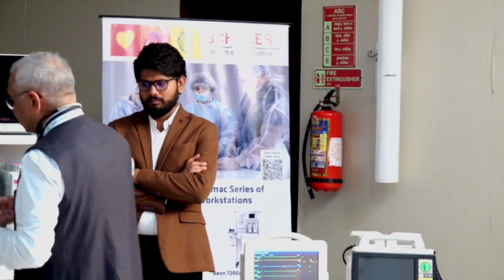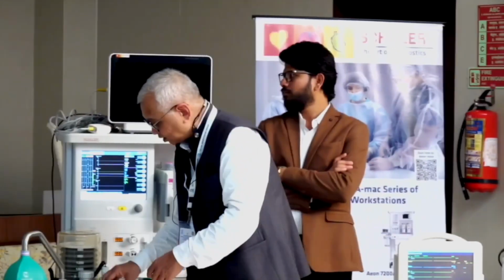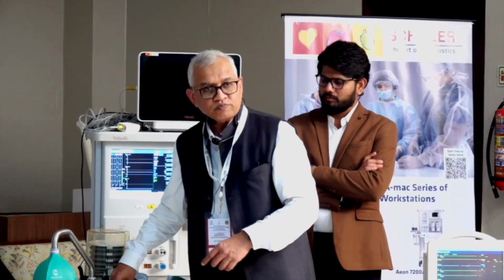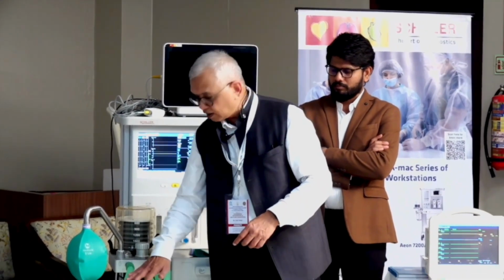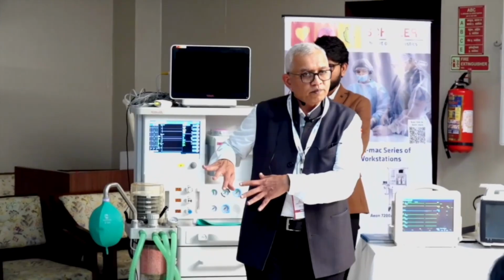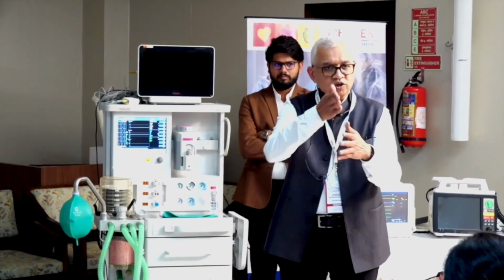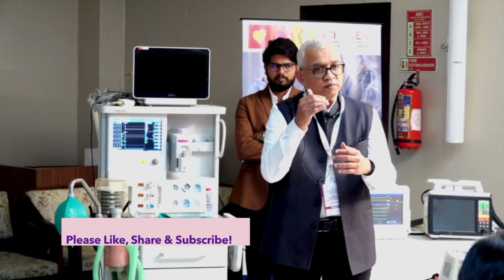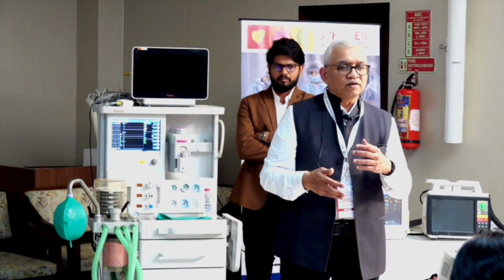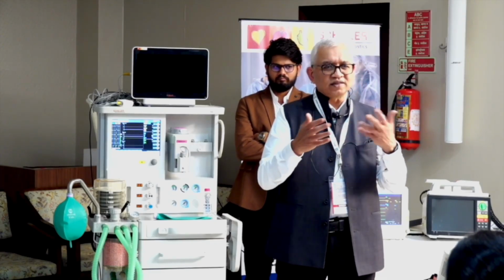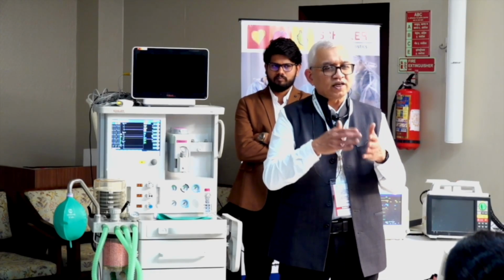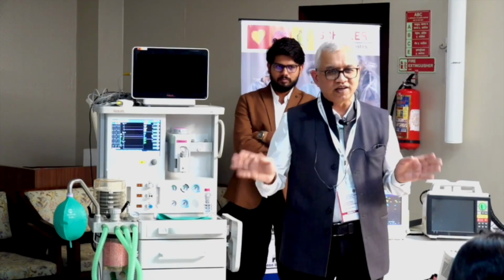But if it is beyond that, it will show if you are giving very high flow. When you are giving very high flow, the oxygen flow which is more than the patient's requirement will also go to the expiratory limb, because the flow is constant, and then the ventilator might sense a slightly higher tidal volume. So a 10% range is okay. If it is slightly more than or equal to the delivered tidal volume, we are very happy.